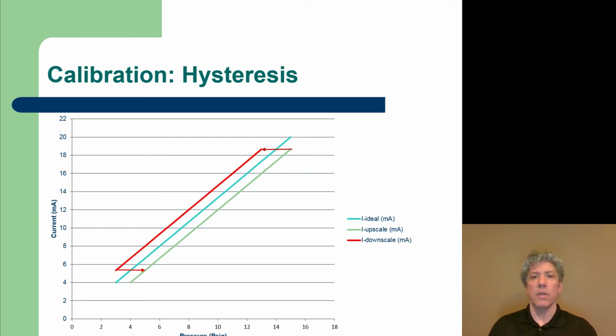That is hysteresis. In current to pressure transducers, the amount of pressure you get for a given current signal will depend on whether the input current is increasing or decreasing. And so measuring the hysteresis is also very important.